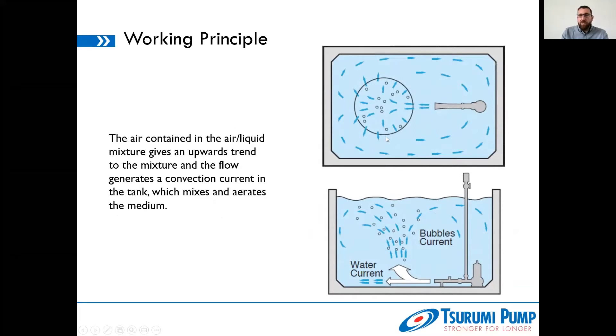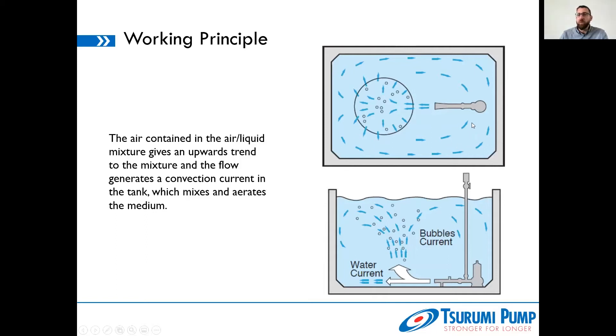You can see two pictures on the right side. The first one is the view from the top — you see the machine with the diffuser and the area where the rising bubbles are shown by the small circles, while the blue arrows indicate the streaming created by the machine. Checking it from the side in the second picture, you can see why you have these defined areas: the bubbles physically rise after a depth aeration effect, and the water current creates a convection effect where the streaming leads back to the machine as the medium is sucked back in.